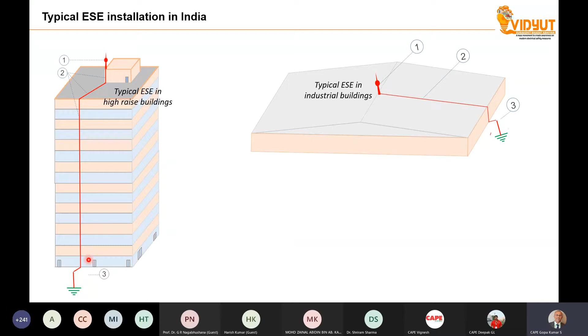Why insulated conductor? Because people say that due to the insulation, the current will go through the conductor without damaging nearby things. So insulated down conductors are used, and there is one earth pit. Mostly the promoters of such systems say this is a very simple system - one rod, one down conductor, and one earth pit. All your problems are gone.